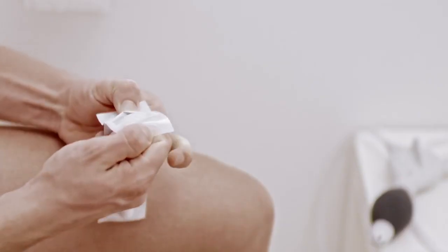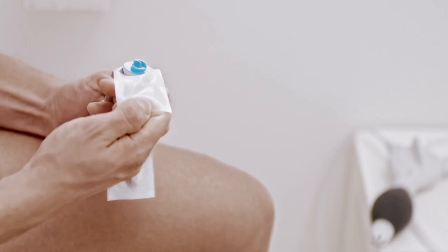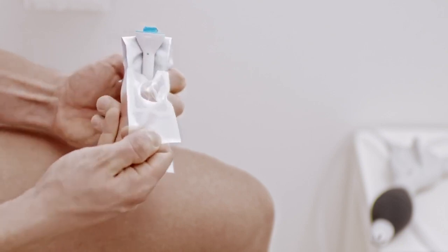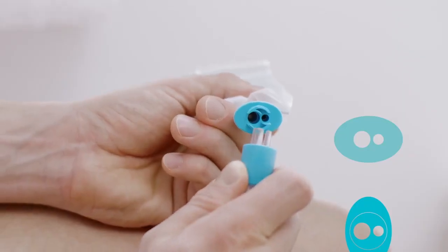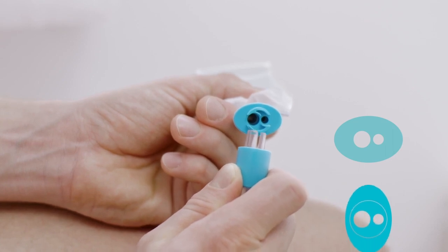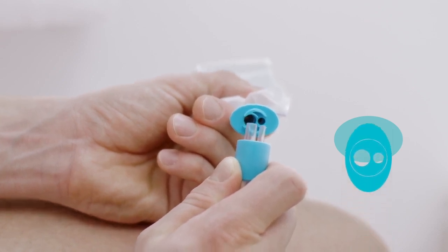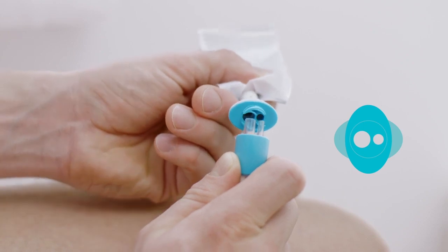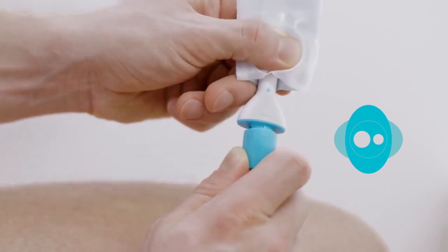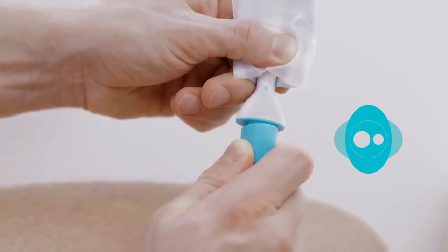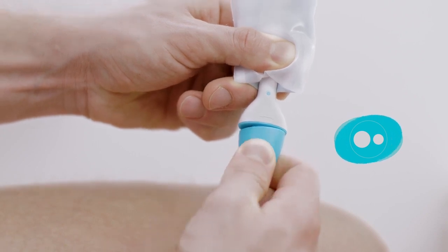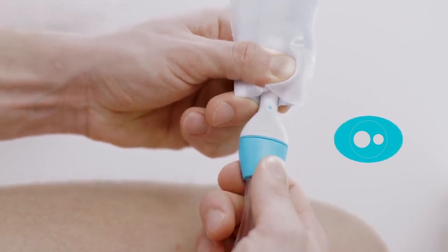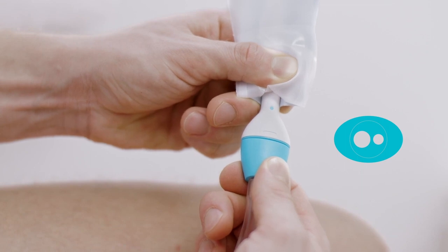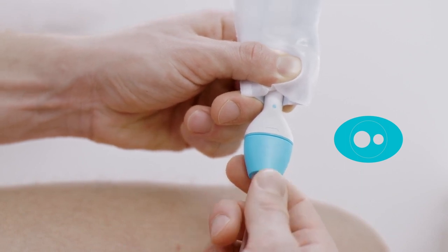Now, slightly open the catheter packaging to the turquoise dot on the catheter. Attach the other end of the turquoise tube to the balloon catheter by aligning the big tube with the big hole and the small tube with the small hole. Make a T, and then twist the connector clockwise until you feel a subtle click. The connector is now locked. Do not inflate the balloon yet.